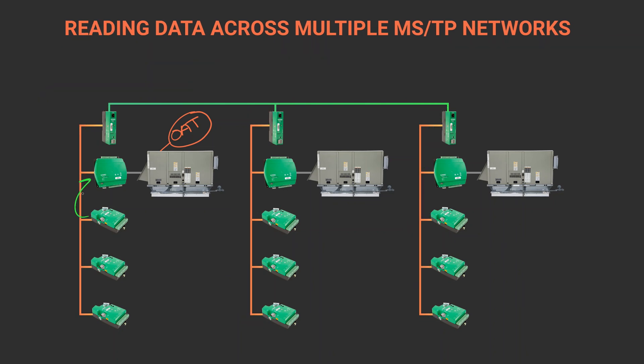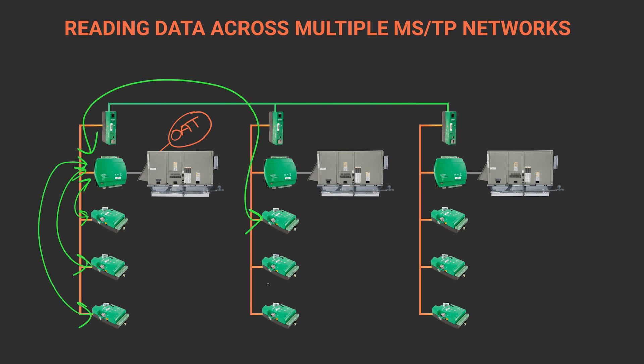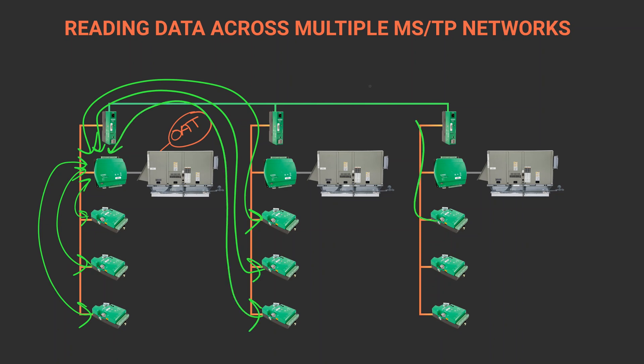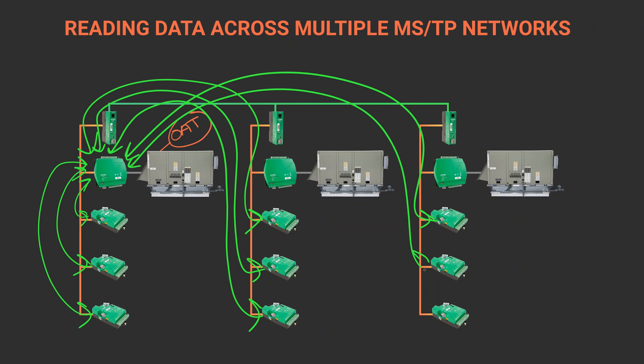Another way would be to have each VAV read the data, but again, we'd have the same amount of network traffic. With either reads or writes, the outside air requests will all travel across multiple networks to get the outside air value to all the controllers in the system, and all the network segments will see all the messages.